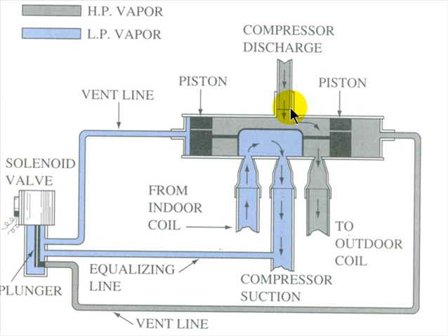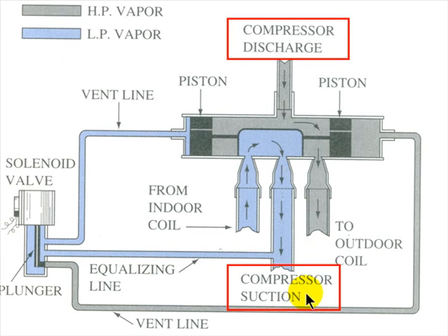Of the four pipes, the one on its own, the only one on this side, is always, and this is on a test, connected to the compressor discharge. Of the three on the other side, the one in the center is always connected to the suction side, the true low side of the system. Either the accumulator, or the true suction line if you don't have an accumulator, whatever the case is. These other two just switch the entering gas from high to low, or inside to outside. That's all they do. That's their only function.